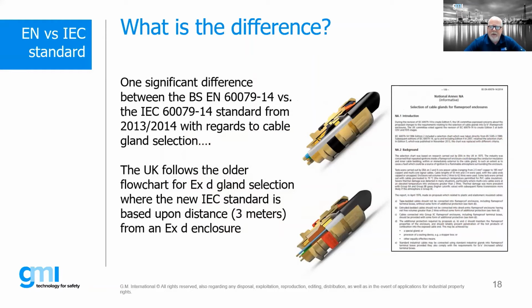The installation and design standard, dash-14, made a big change in 2013 on the selection of cable glands for use for direct entry into flameproof boxes. So what happened is the UK disagreed with what the IEC had actually published, but they couldn't change the standard because it was adopted by CENELEC.